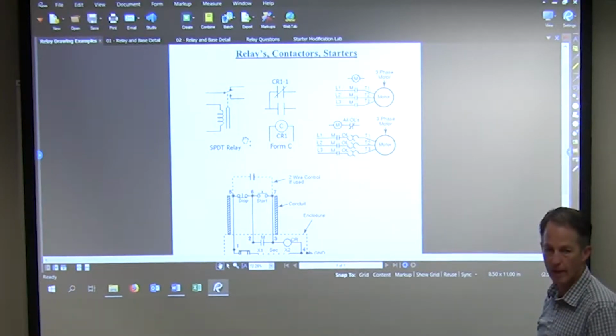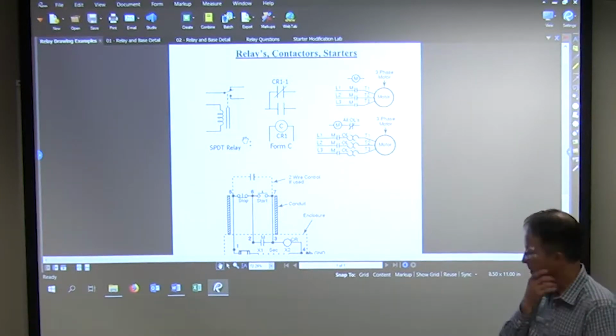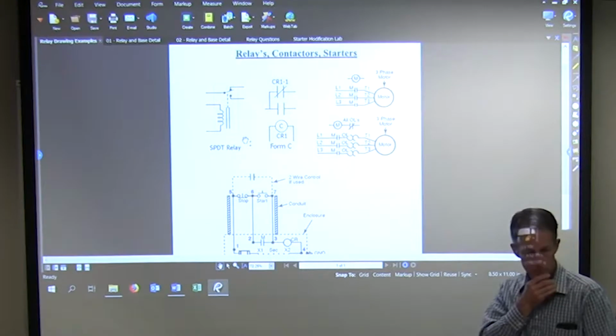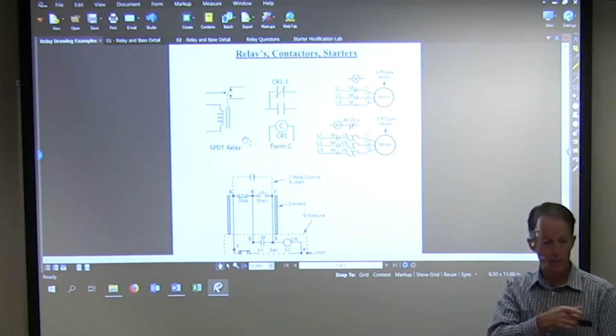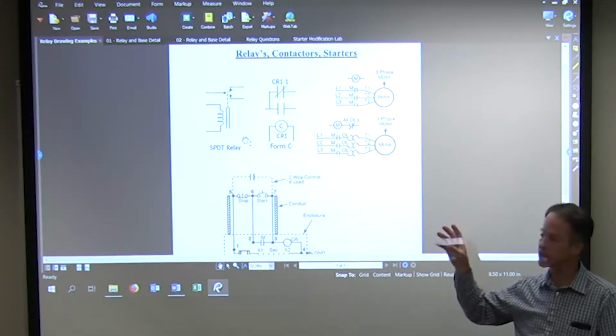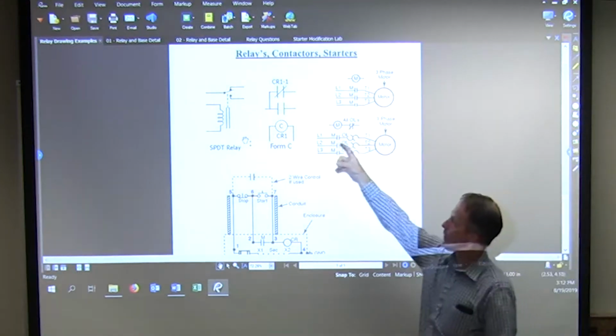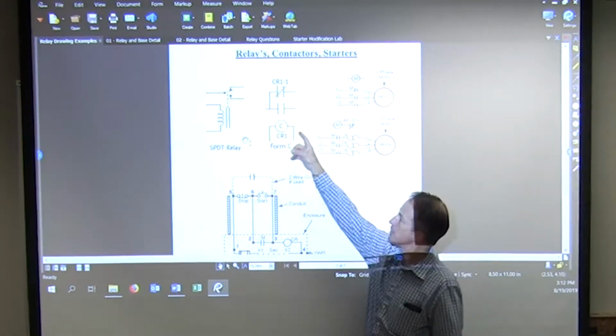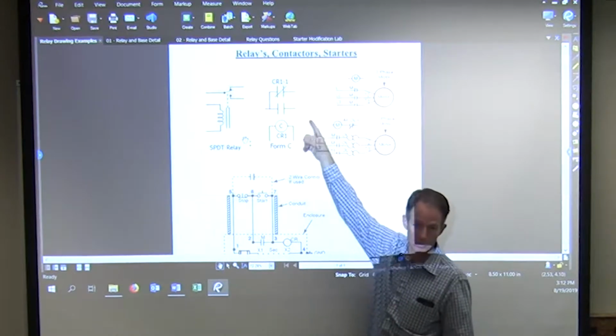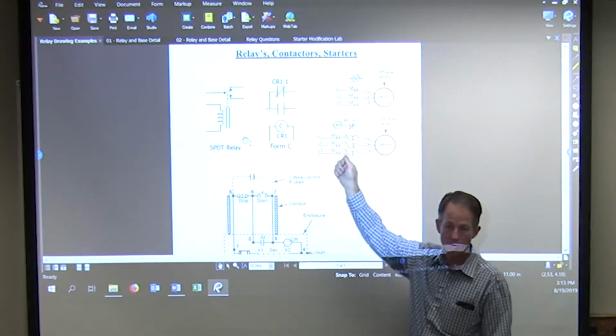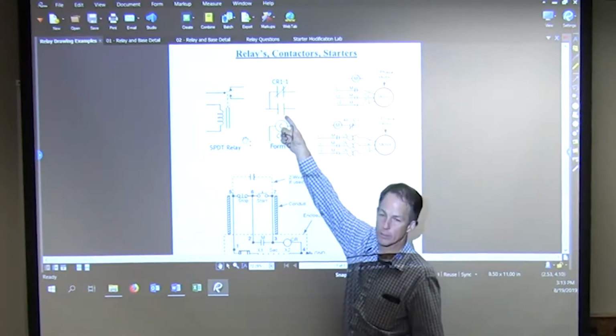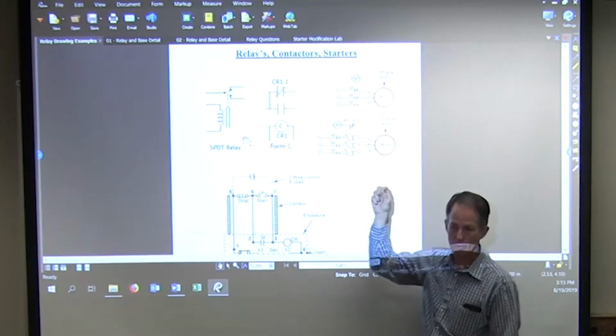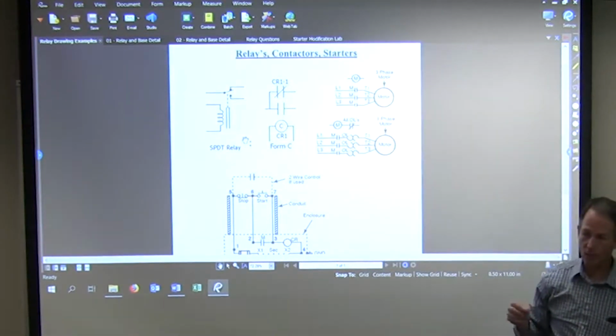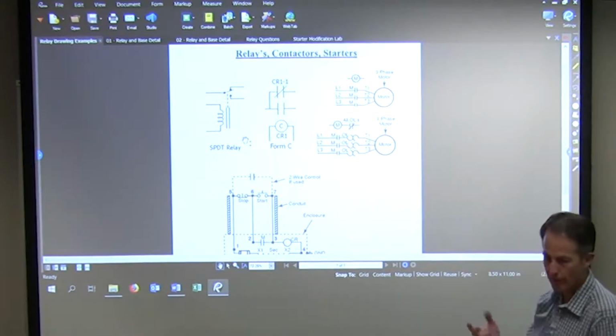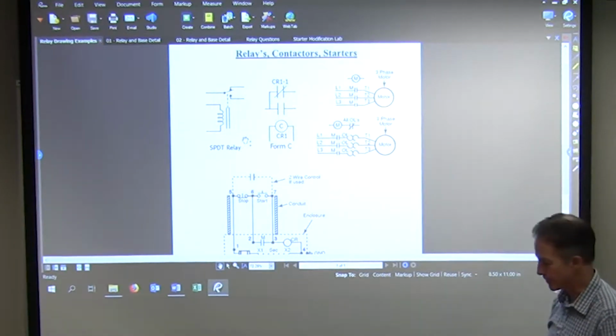Anybody know what a Form A or a Form B is? Relay. Would it have to do with a socket or its shape? Okay, it's a good possibility, but in this case, it has reference more to what's available. So Form C has both a normally open and a normally closed contact. A Form A would just have normally open. Form B would be just normally closed. Okay, Form C has both. And so that's kind of the way that they're described.